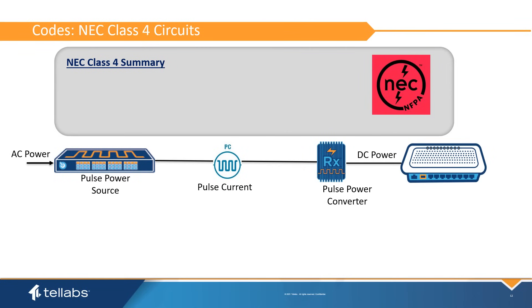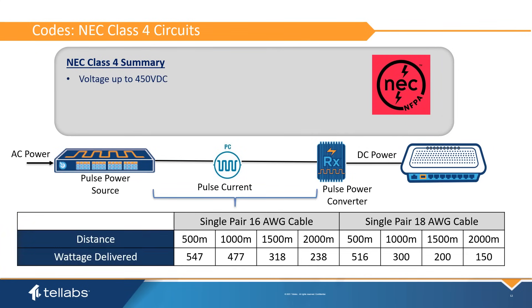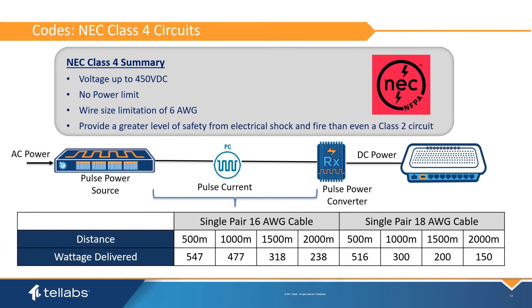Class IV is a new circuit term defined in 2023 in the NEC. Class IV systems are referred to as fault-managed power systems. Class IV power can deliver higher wattages and longer distances than Class II. These systems are not power limited and can deliver hundreds of watts of power. They intelligently limit the amount of energy that can go into a fault, mitigating the risk of shock or fire and allowing installation using methods much like power limited circuits.